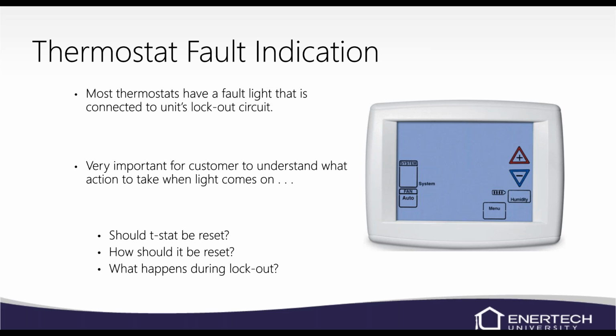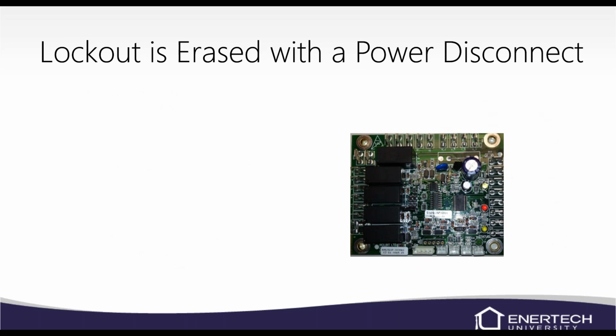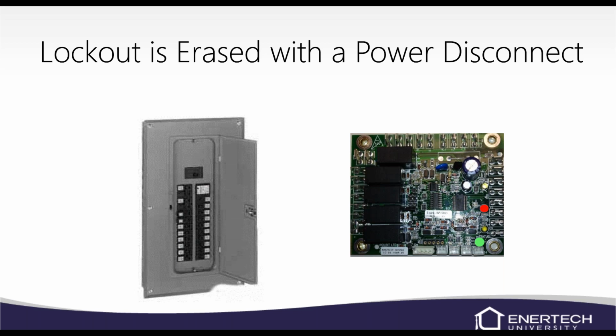Now, should they turn off the power to the unit? Should they reset it at the thermostat? What happens during a lockout? So basically, if we go to the breaker or to the disconnect, the high voltage to the unit, and we remove it, the lockout is erased from the unit. We don't have that battery backup. So if you want to know what that lockout is when you get out there, the best way for the homeowner is not to go to the breaker and shut it off there and turn it back on.